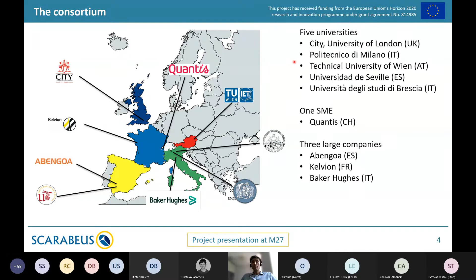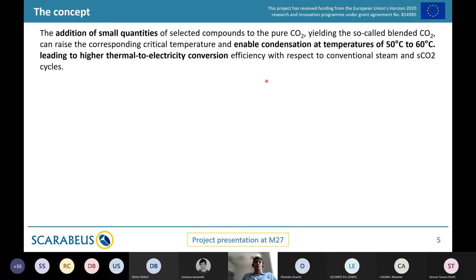As stated, the concept is to add small quantities of select compounds to pure CO2 so that condensation can occur even at temperatures of 50 to 60 degrees C. This means that even with ambient temperatures of 35 to 40 degrees C and an air-cooled condenser, you can still have a condensing cycle in the power plant.